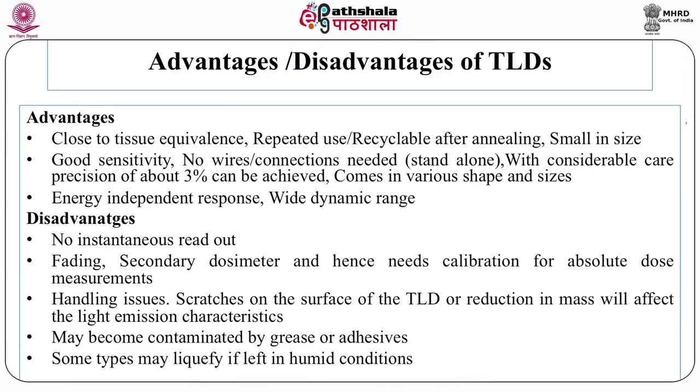Among the disadvantages of TLDs is that there is no instantaneous readout like you have in the semiconductor detectors. Then there is a problem of fading, and hence it needs calibration for absolute dose measurements. Then there are handling issues. Scratching on the surface of the TLD may lead to reduction in its mass, or its response may become contaminated by grease or adhesive, which can change its response. So these are some of the disadvantages of TLDs.